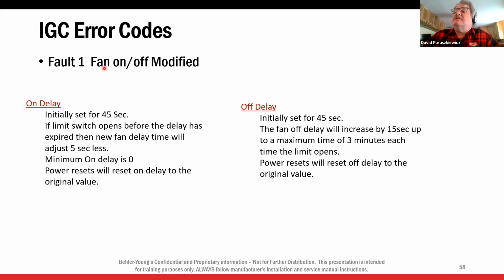All right, so fault one, it's not really a fault. If it's flashing one time, it means the blower time has been altered in heating. So it will alter itself. These are the conditions in which it's altered. Initially, it's 45 seconds. If the limit opens before the blower starts, so the burner comes on, and before that 45 seconds the limit trips, 5 seconds will be deducted from the blower on time. And it'll continue to deduct 5 seconds all the way down to 0. So the blower could start instantly. But for that to occur, the limit has to trip before the blower comes on. The off delay: the blower will shut off after the burner shuts off in 45 seconds.